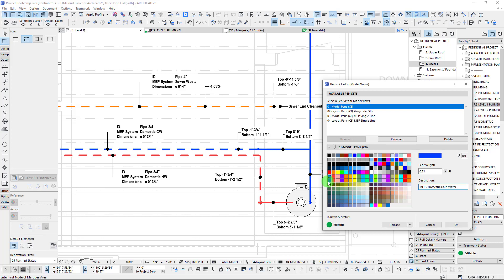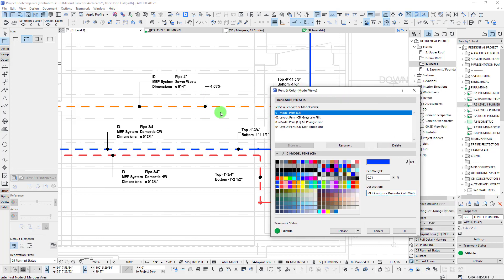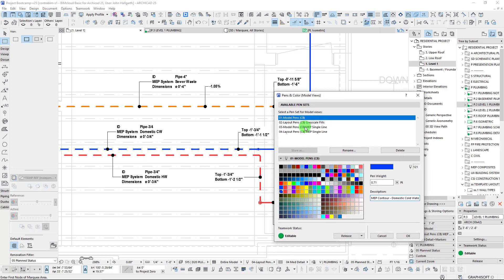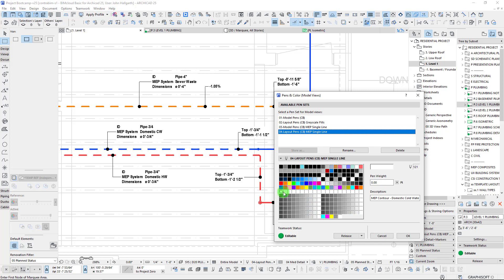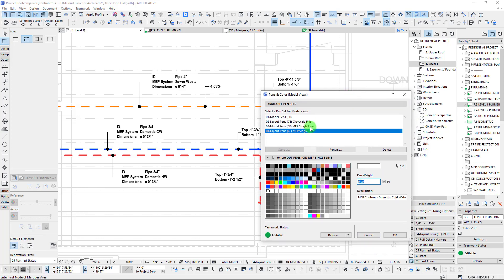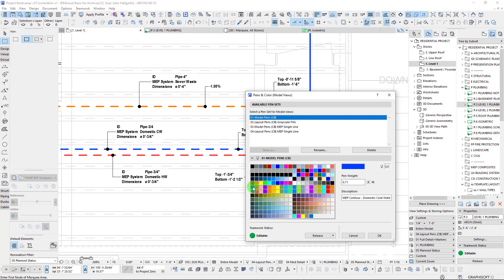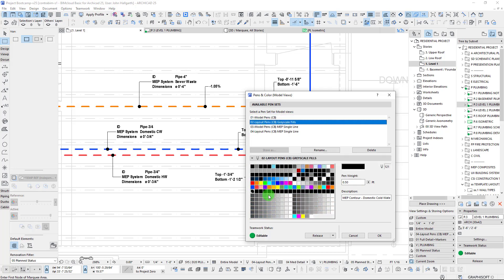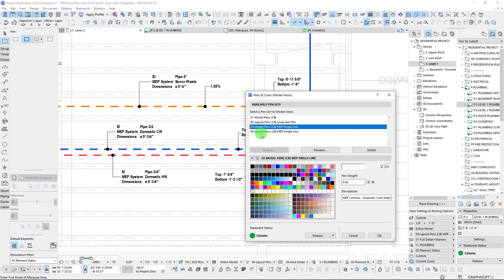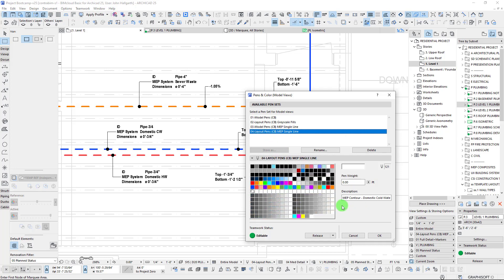Our second row here, which at first look is the exact same pen, is actually our contour pens. The reason we've done this is: when we want to see the full system including the center line as well as the contours in the same color, we can use both of these pens for those MEP systems. But when we jump from model pens to layout pens, this entire row goes white — to a zero pen or zero thickness. That's the trick: we switch from full colored pens on our contours and center lines to a hairline white pen.